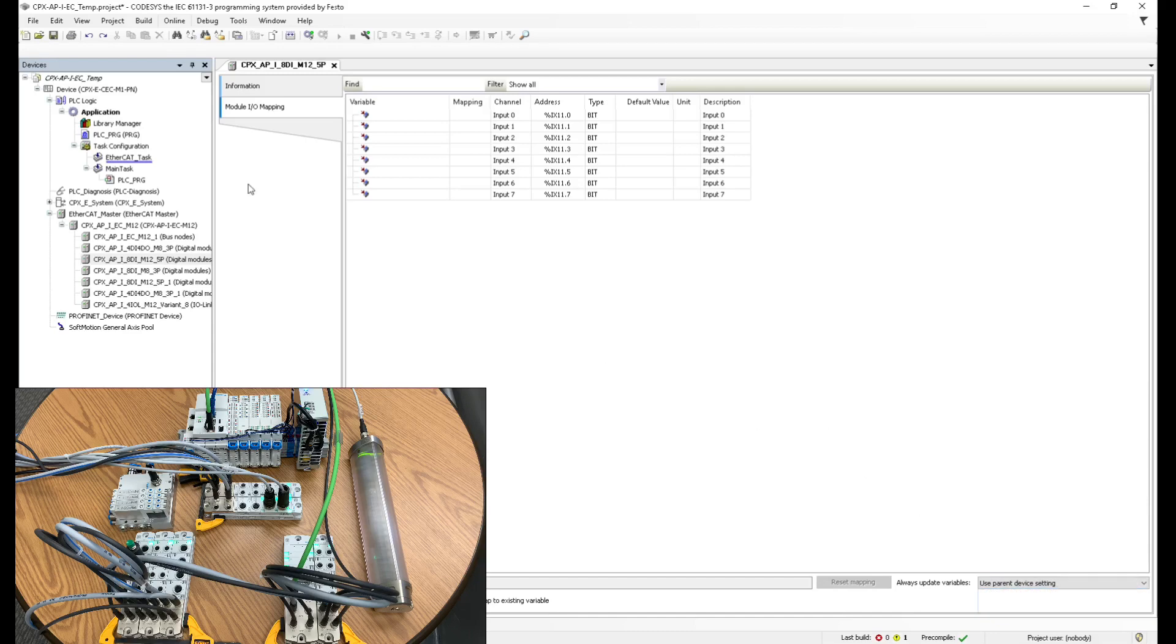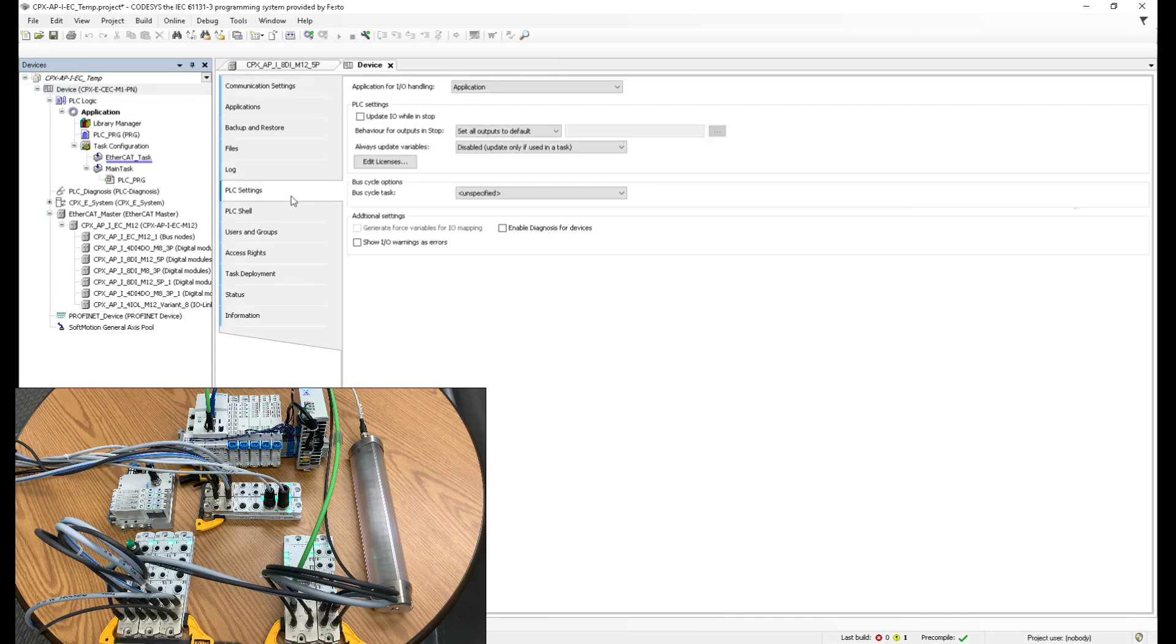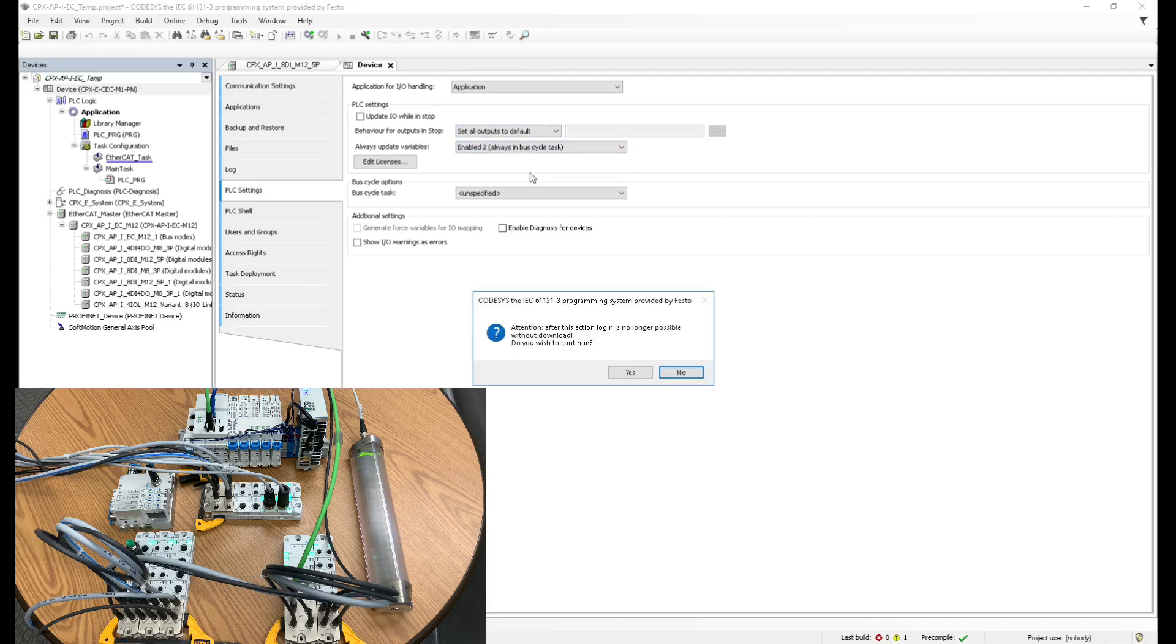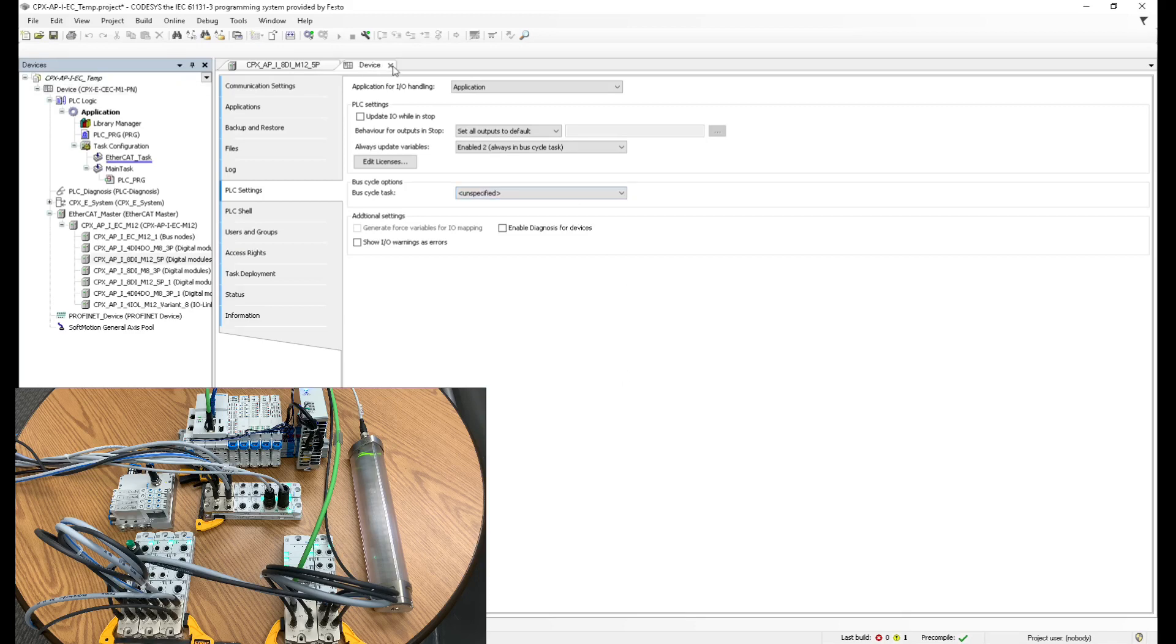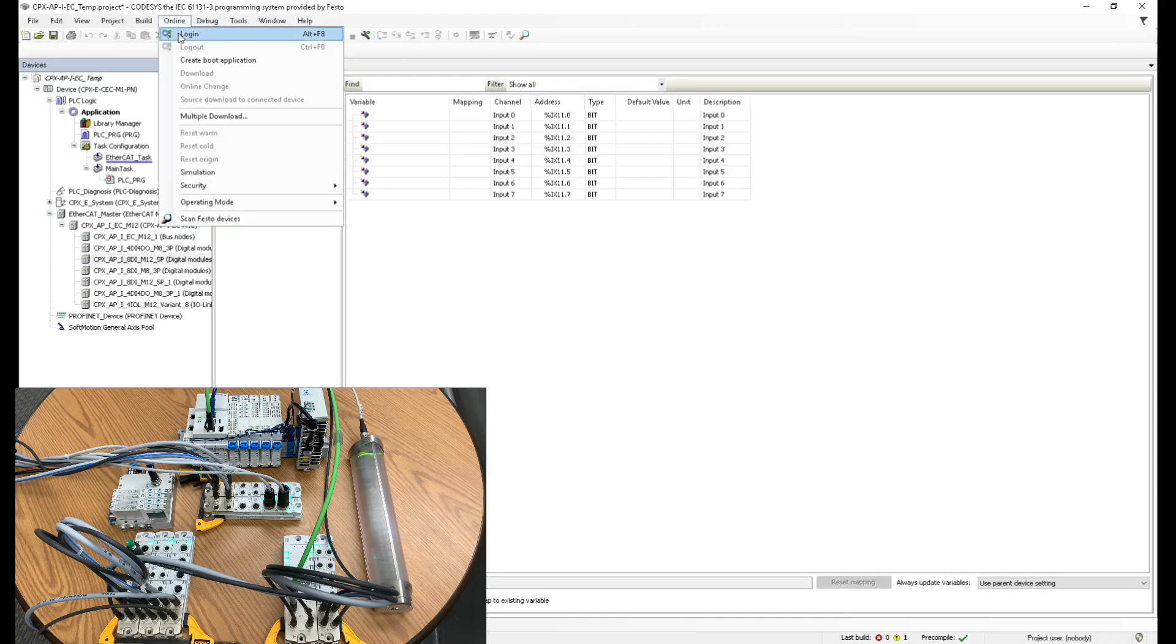Usually the other thing that I do is you can go back to the device, click on PLC settings right here, and then you can change this. Always update variables. You can change this to enable, and then yes, we close this and we download again. And now we should see the change whenever it happens.